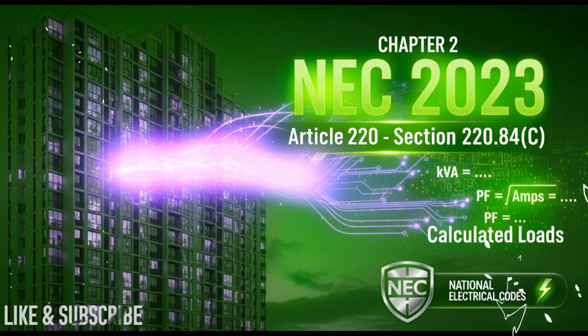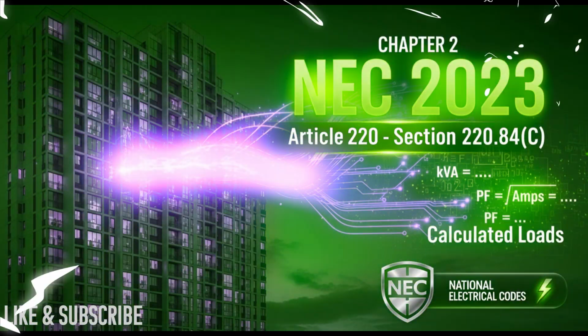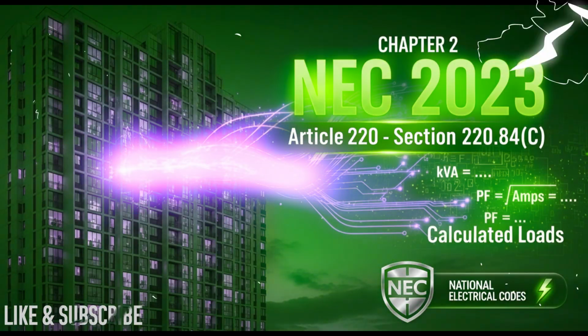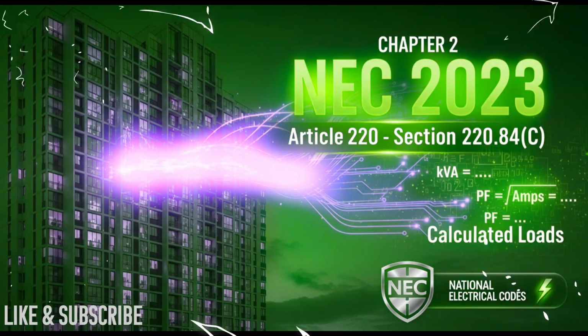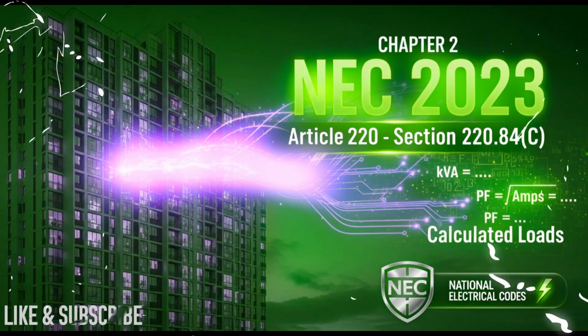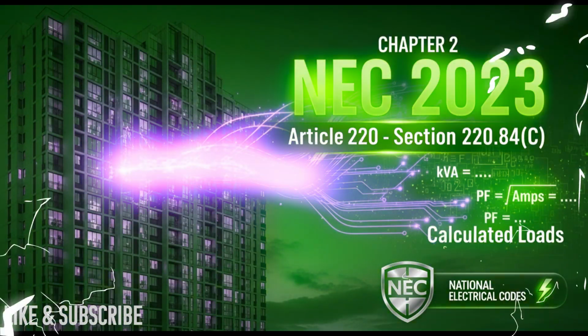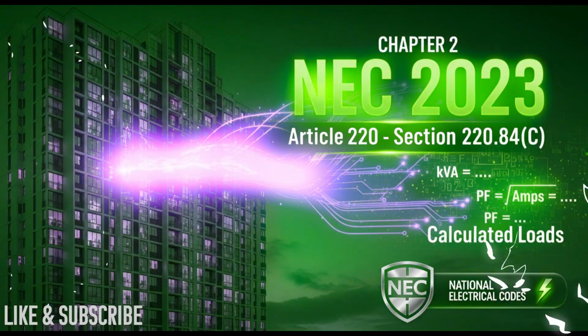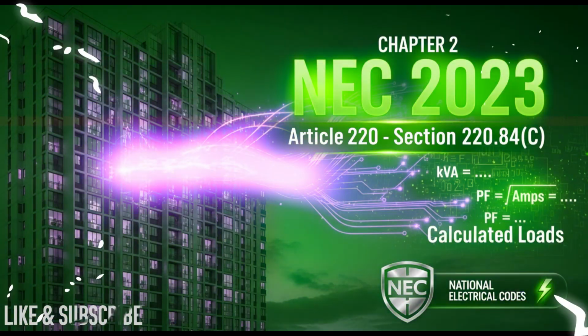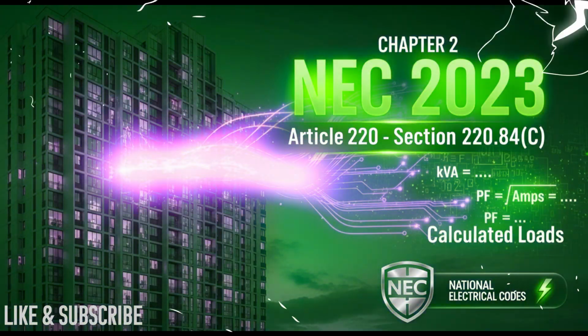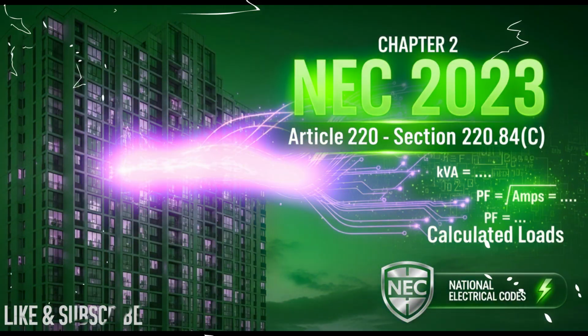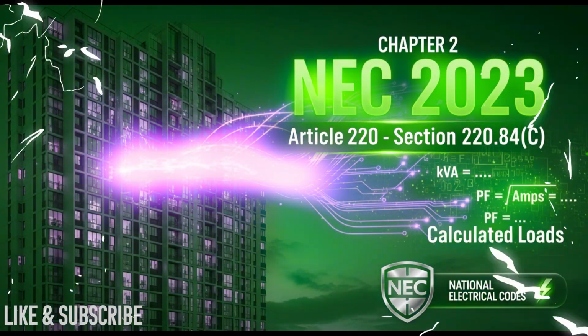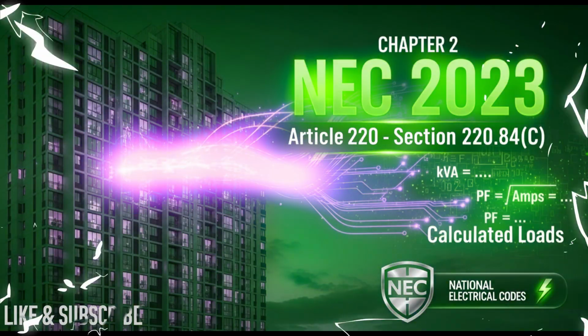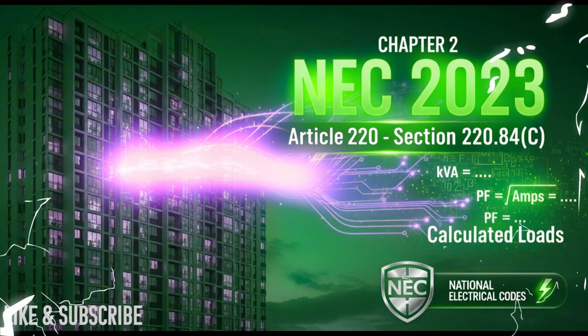And our sources list 5 distinct mandatory categories under 220.84(C) that you have to add up for this initial big calculation. Okay. And this is maybe the aha moment for someone learning this. These 5 things aren't just an engineer's best guess, are they? Not at all. The code actually dictates specific numbers, specific volt-ampere figures that must be included. Mandatory. It forces conservatism into the design. It basically takes subjectivity out of the equation for these minimum safety levels. Safety first, right? Always. And hey, speaking of safety and numbers, let's quickly define a term we'll be using a lot: VA, volt-amperes. Okay, VA. It's essentially the standard way we measure electrical load in the code. For a lot of these calculations, it acts pretty much like watts, but VA is the official unit here. Good to know. So every time we say VA, think power required. Okay, let's break down those 5 required inputs, the ones in 220.84(C) that build up this baseline load.